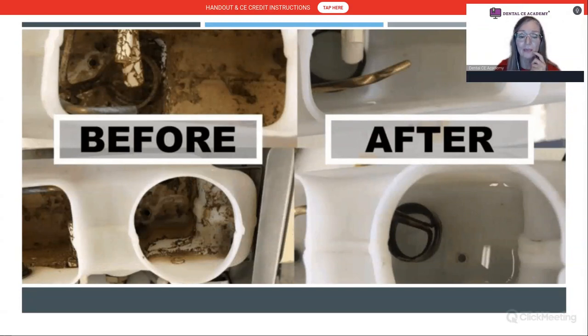I was in a situation once where they weren't monitoring the autoclaves at all. I was working on a patient, turned around, and saw an autoclave flashing an error. It was a little child, and I asked the assistant, are these instruments sterile? She said, yeah doctor, they came out of the autoclave. I said, that autoclave's saying error, let me see your maintenance records. They didn't have any because they weren't testing their autoclaves. So I had to go to the lead dentist, and they had to shut the clinic down because they couldn't demonstrate their instruments were sterile.